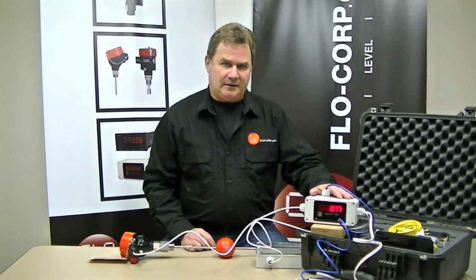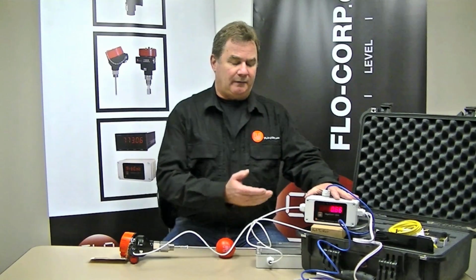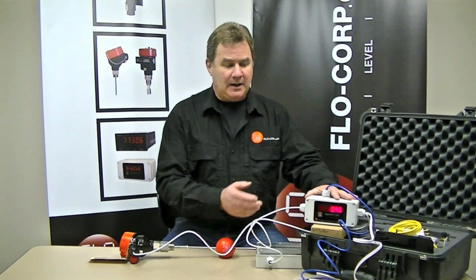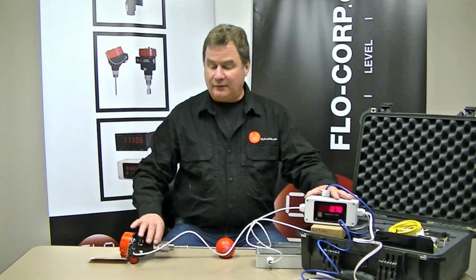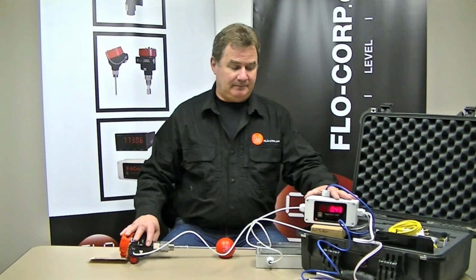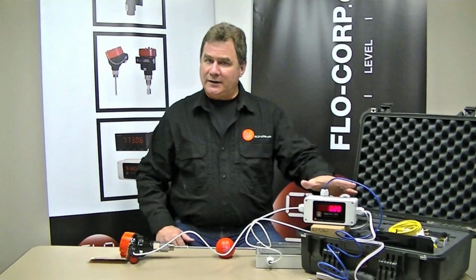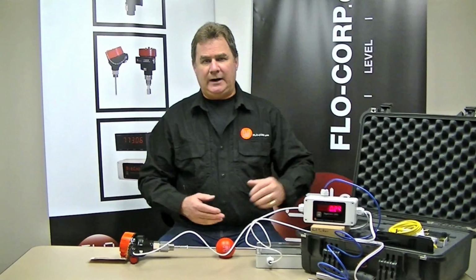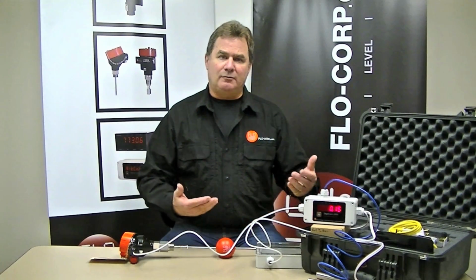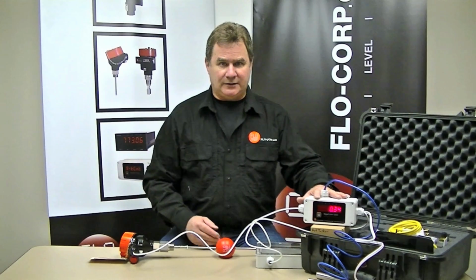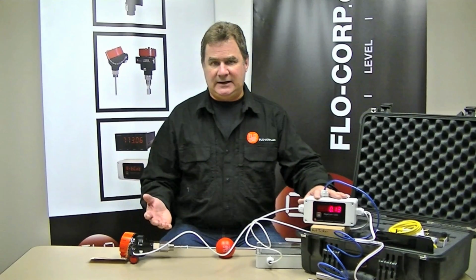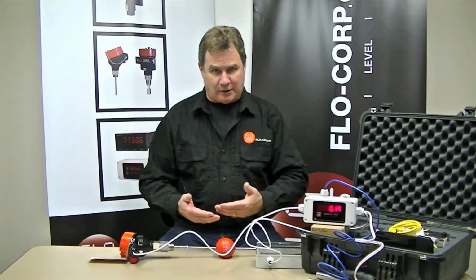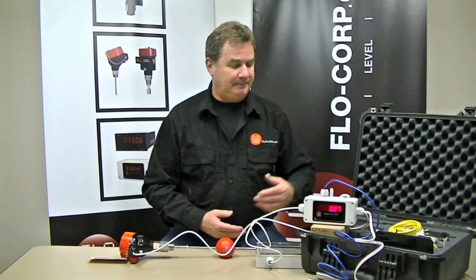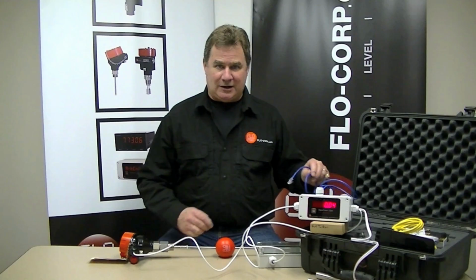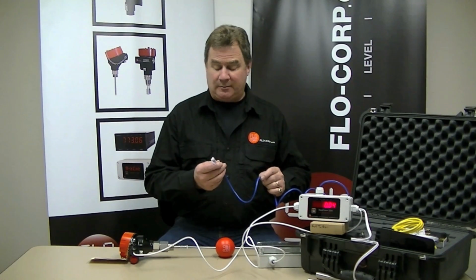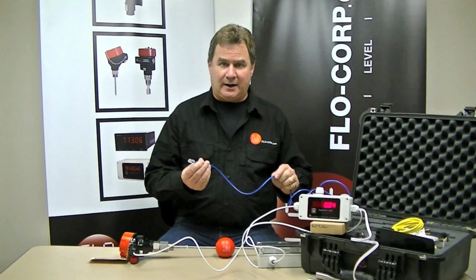The Digicom 2000 is the level monitor with a 4 to 20 milliamp output. It supplies the control power for the tracer, 24 volt DC. It also has an RS-485 output. The RS-485 output is so if you want to monitor the Digicom 2000 and tracer level monitoring system through your PC, you can come in through your COM port, USB traditionally. The second computer communication output is the Ethernet output that can be connected into a standard plant-wide area network.